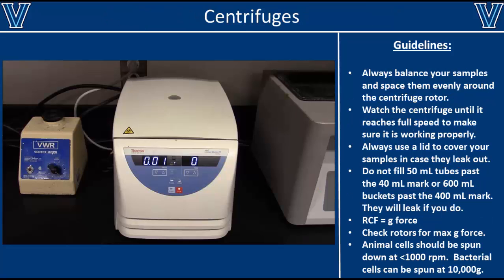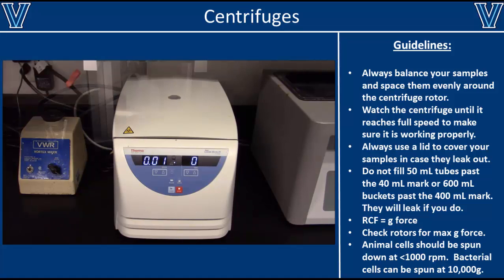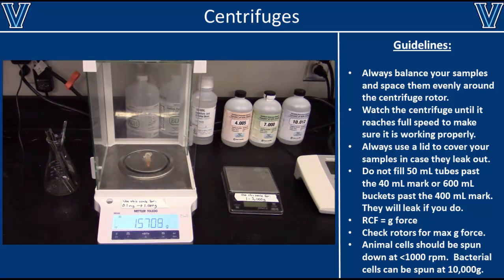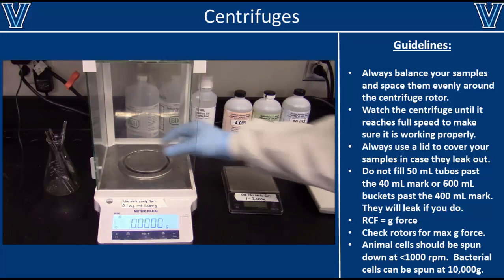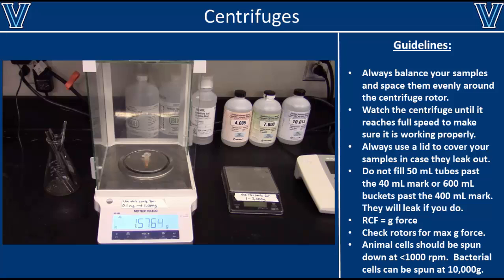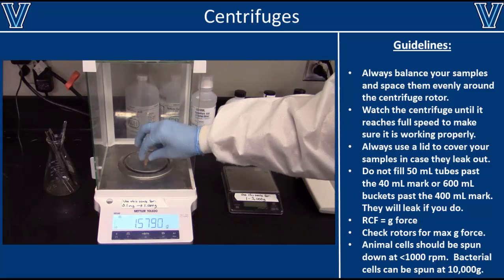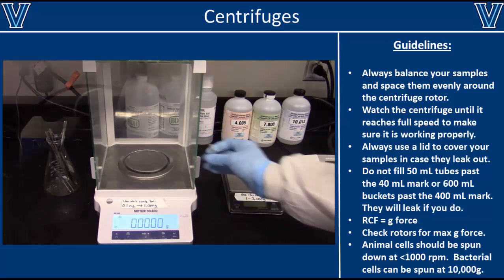Centrifuges are also commonly found in most labs. They're used to separate particles of different densities by spinning them rapidly to generate a high G-force. Since most centrifuges do operate at rather high speeds, it is important that you know how to properly use them to avoid damaging the centrifuge or harming yourself. The most important thing you need to know about using a centrifuge is that any samples you put on the rotor must be properly balanced. Use an analytical balance to make sure the weights of your samples are equivalent and adjust them as necessary.